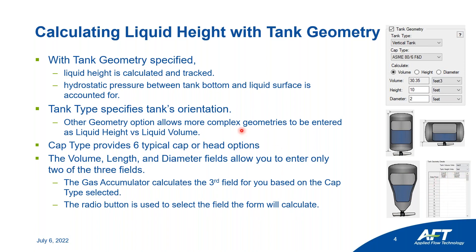The cap type dropdown provides six typical cap or head options — for example, ASME 80/6 flanged and dished, shown here. Below that you can see the volume, length, and diameter fields. They allow you to enter two out of three of the fields and we will calculate the third for you. So if you want us to calculate volume, you select the volume radio button, enter your height and diameter, and for that given cap type we will give you the volume that your gas accumulator tank will be.